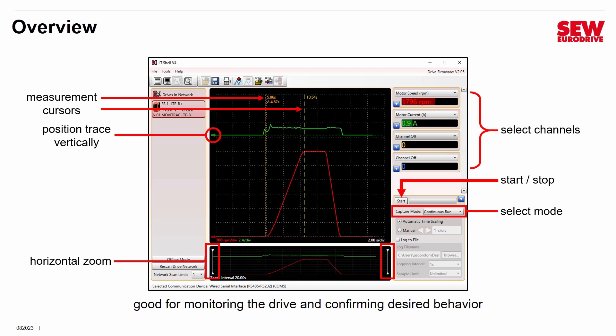There are two measurement cursors — they start on the right and left side of the screen. As you grab them and slide them over the trace, you will see the value of the traces appear in their channel windows. For example, grabbing the second cursor and moving it shows that at that spot the values are 1796 RPM and 0.9 amps. You can use the two cursors together to take time measurements by positioning them at the beginning and end of an event. This allows you to take measurements on your traces and tells you a great deal about your VFD.